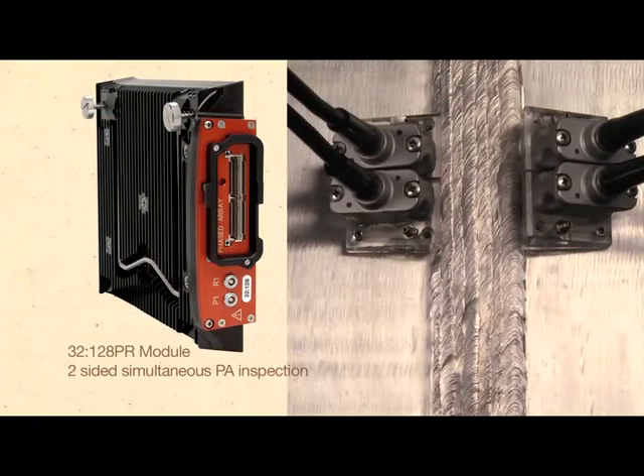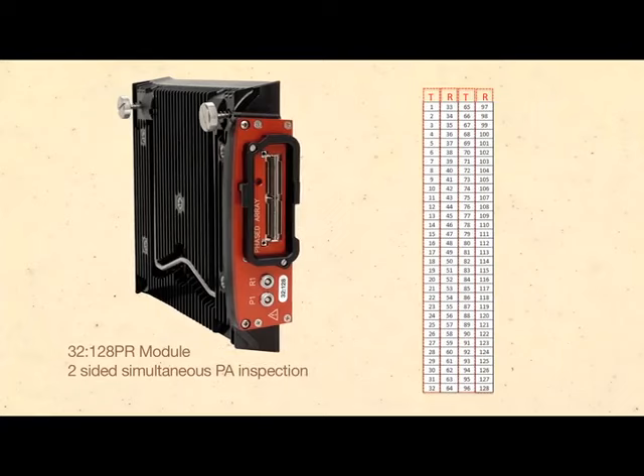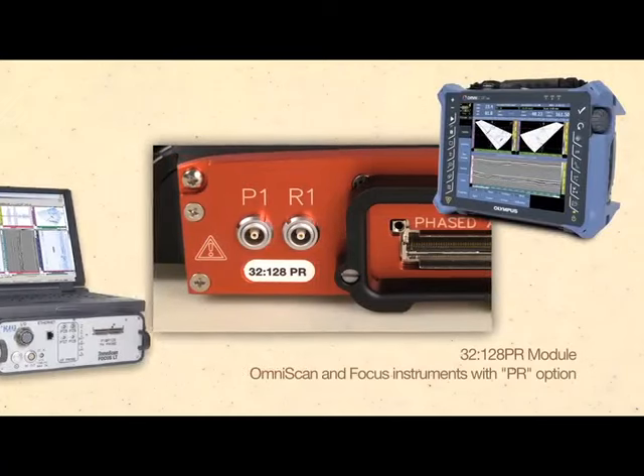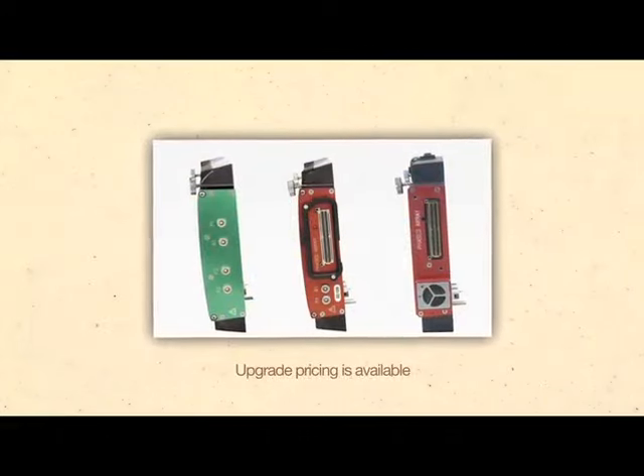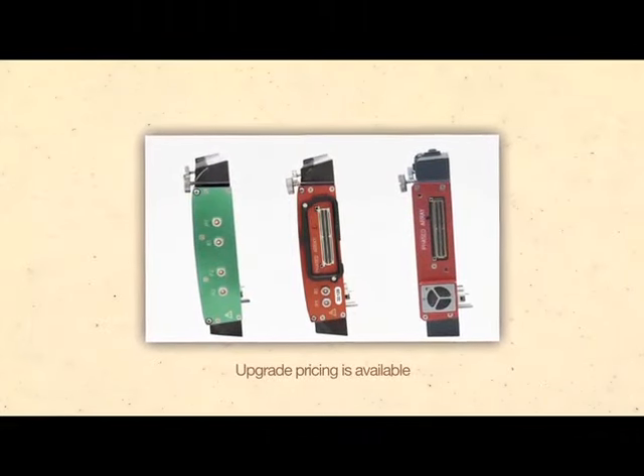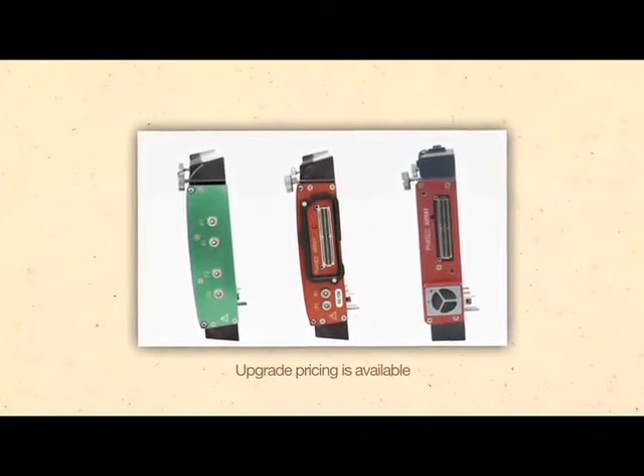Instrumentation to drive PA probes requires the ability to transmit and receive using different elements or apertures available in the OmniScan and Focus instruments with the pulser receiver or PR option. Upgrade pricing is available for standard or previous generation OmniScan modules.